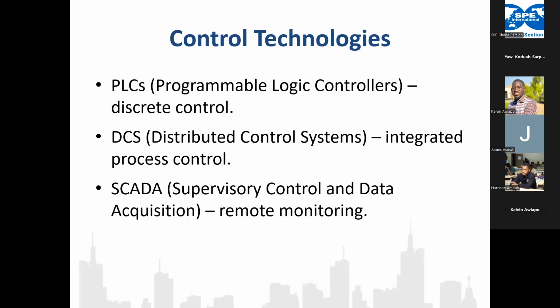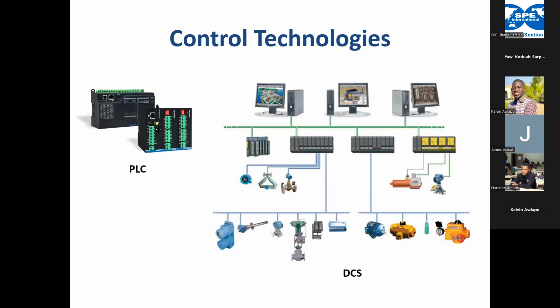So I think I showed something like this here. It's something small like that, and then it is being programmed. It can be programmed to start and stop a motor, a pump, for instance. Sometimes it can be programmed to time the sequence of a process. For instance, you may have a drying tower, maybe in two. It comes in pairs. One will be doing the drying, the other will be in standby. So you can program the PLC so that, maybe after 5 minutes for the drying sequence, it switches.